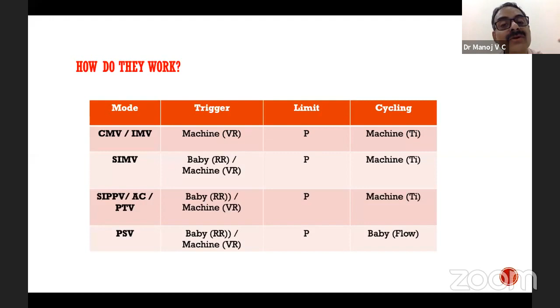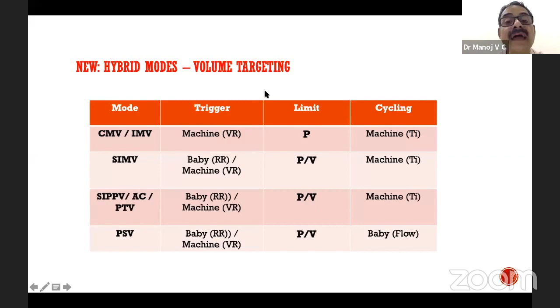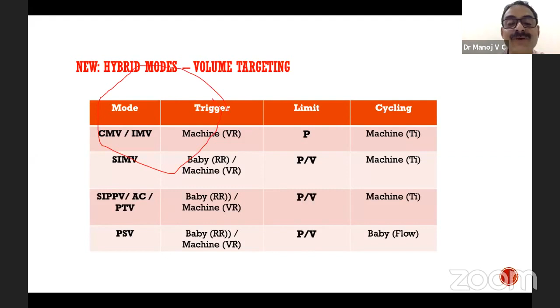Now we said that pressure limit is what we use, but then we want to have the best of both worlds. We know that volume targeting, I began my lecture by saying that what is the parameter that you want to target? Tidal volume or minute ventilation. And I am not showing any volume here. So we started looking at, is it possible? Volume control ventilation is impractical in preterm babies, in neonates, but there is another possibility. You set a pressure limit, and then you allow a particular volume to be delivered, and once that volume is delivered, you cut off the pressure at that. So this is the hybrid mode called volume targeting, which is the mode of the future, or actually the mode of the present in this century. This century, volume targeting is probably what we should be doing. We'll discuss this in the subsequent sessions.